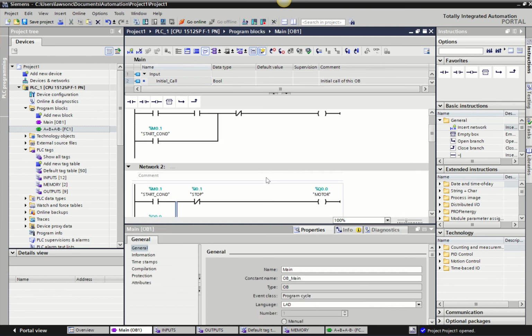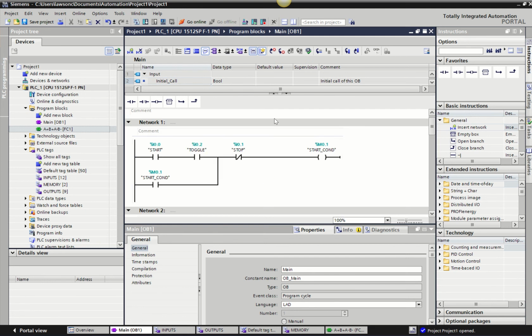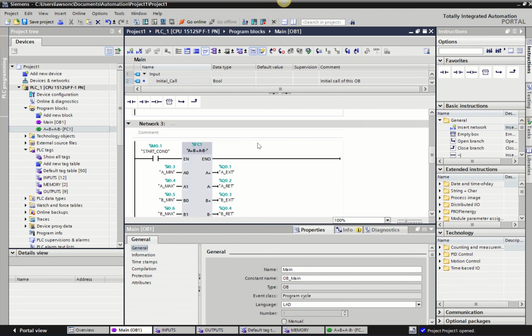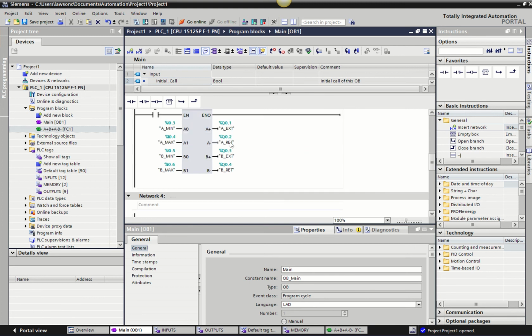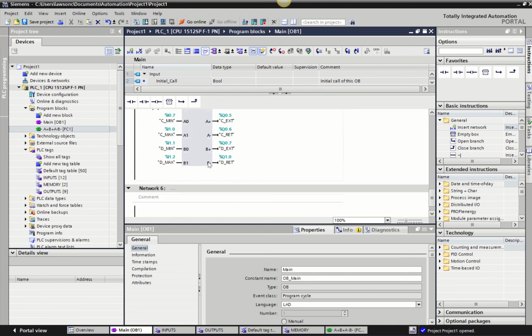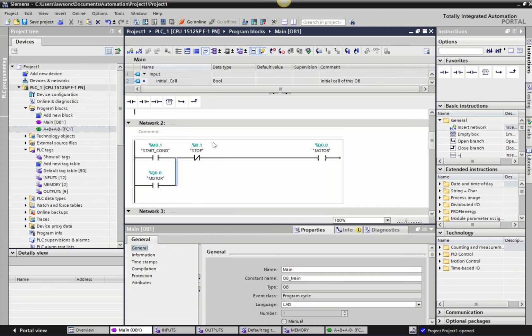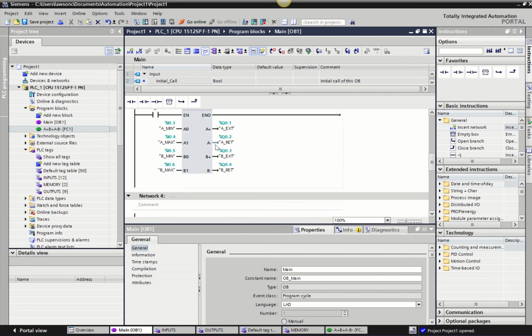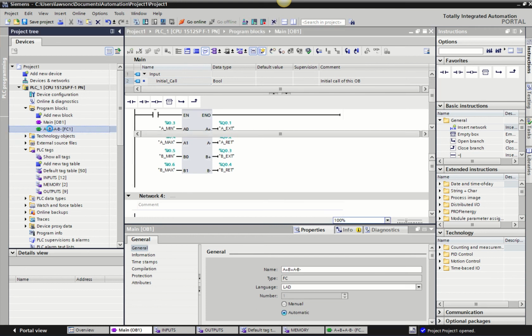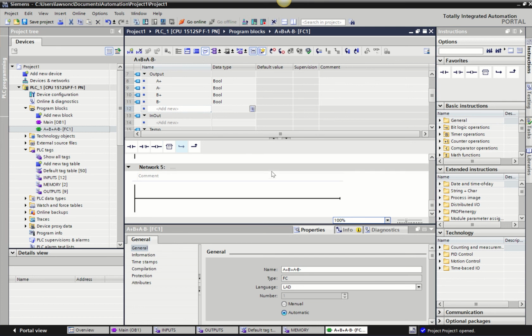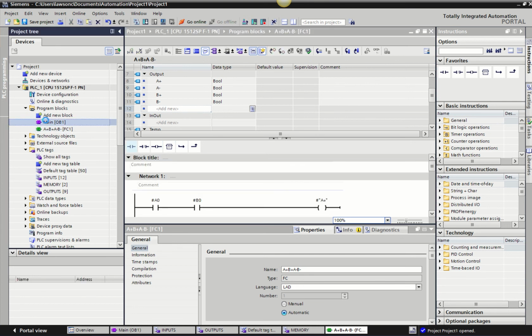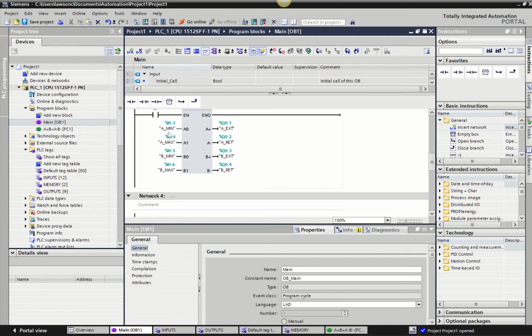Ultimately, again, we start our motor, we have a start condition there, and we see how our motor's turning on. Then we see how the first sequence is triggered, and then how the end condition and our end sequence is triggered. So it's nice and segregated there. If that's running okay, maybe there's a problem with the sequence, and if the sequence is not working, then we can go into the actual code of the function and see, right, maybe there's an issue here with how I've coded the sequence, or maybe there's an issue of how I've linked in the inputs and the outputs. Have I linked them to the correct ones? Is A min referencing the initial position of the first limit switch? Yes, it is, but maybe there was a mistake there.